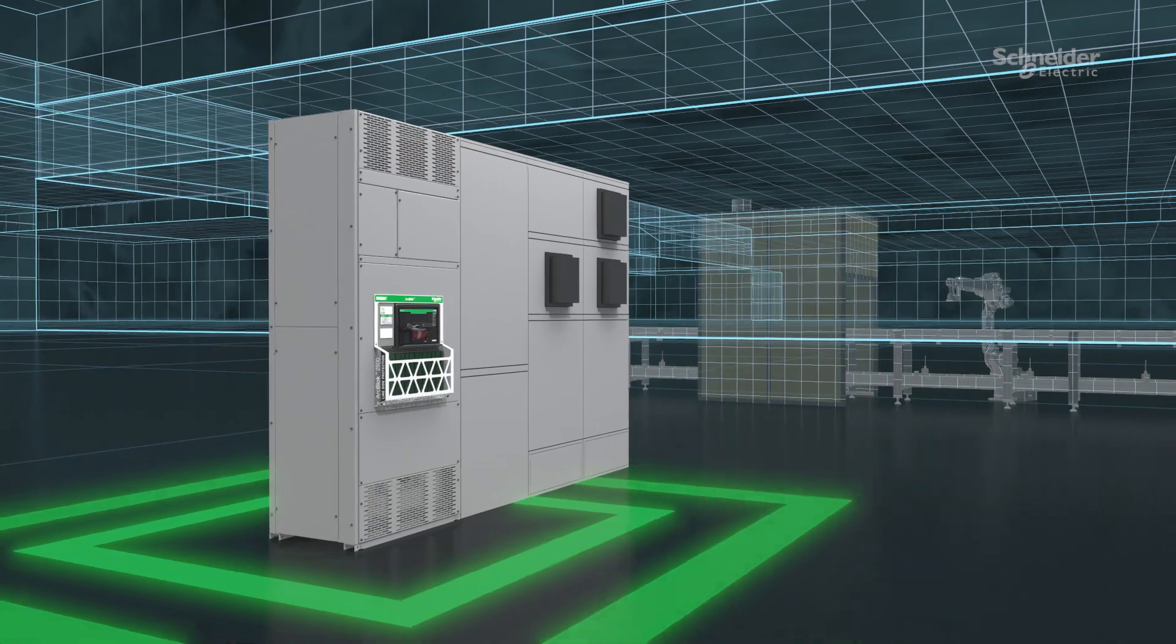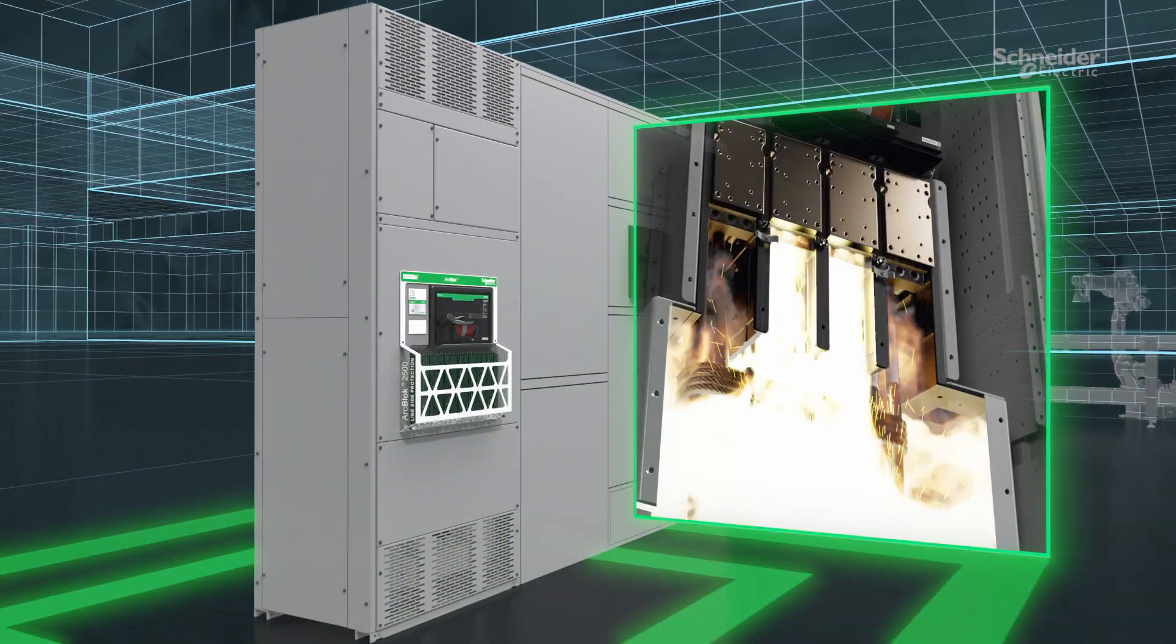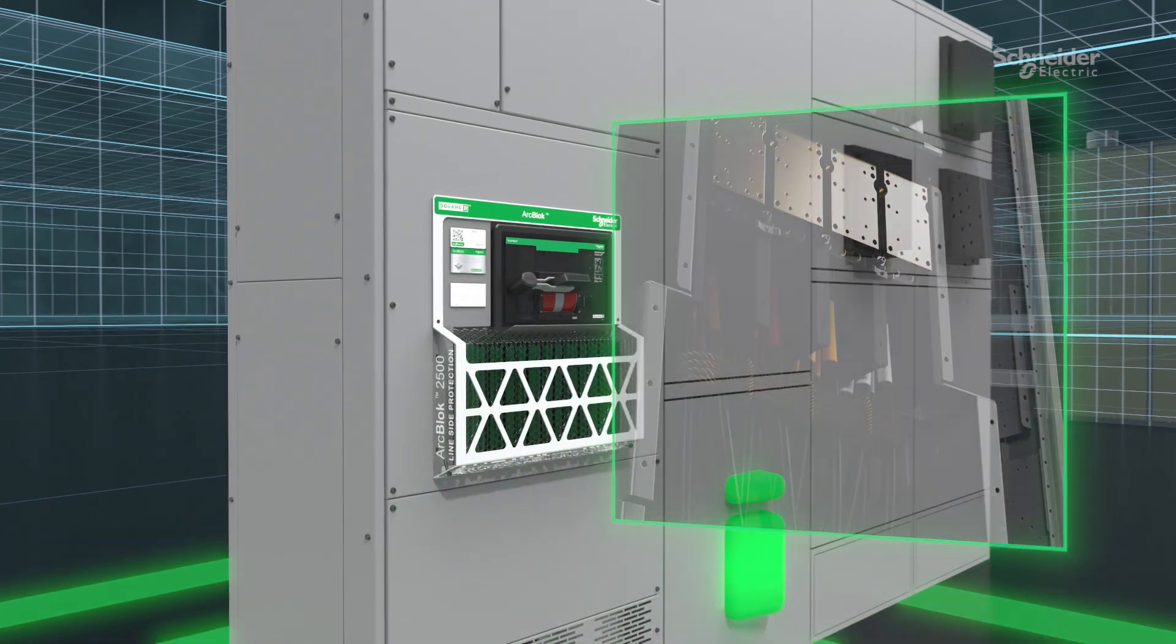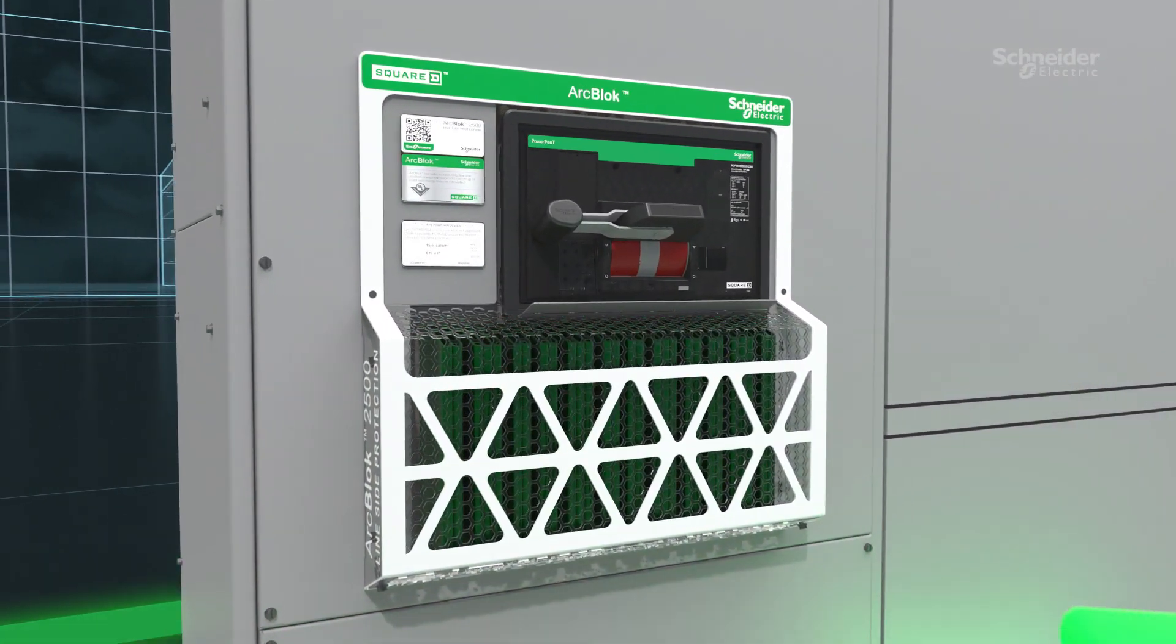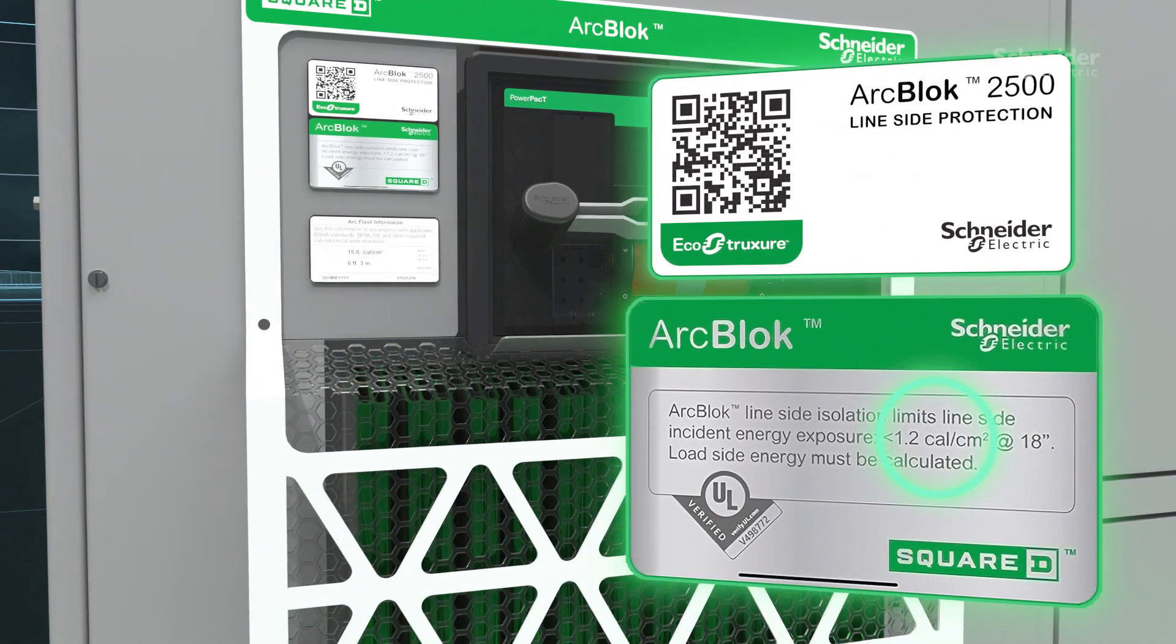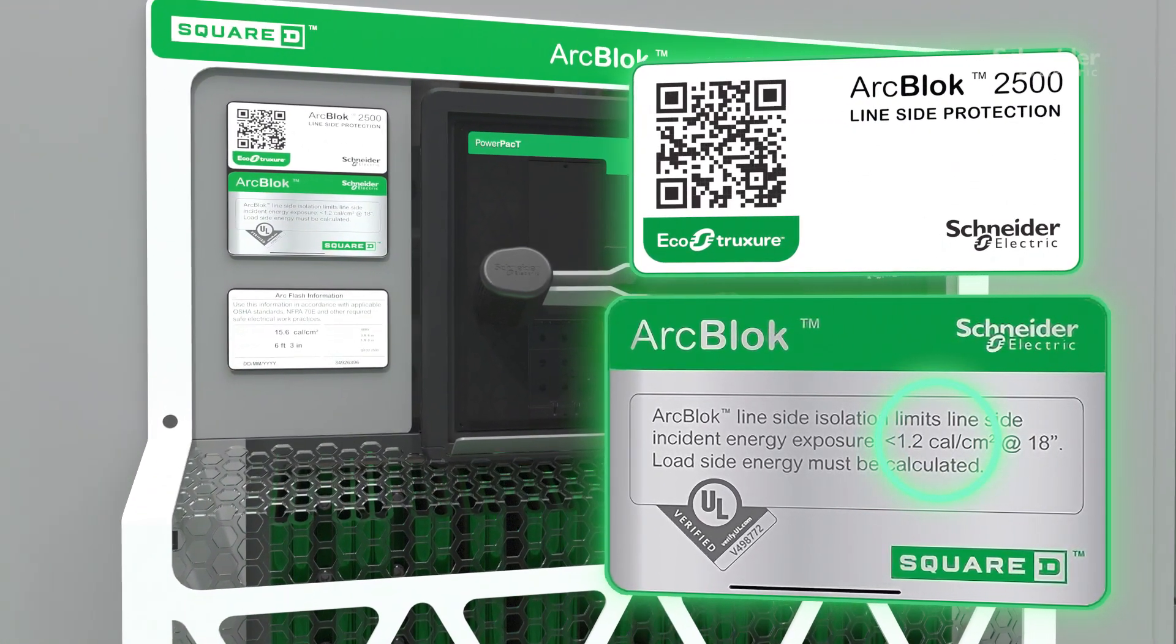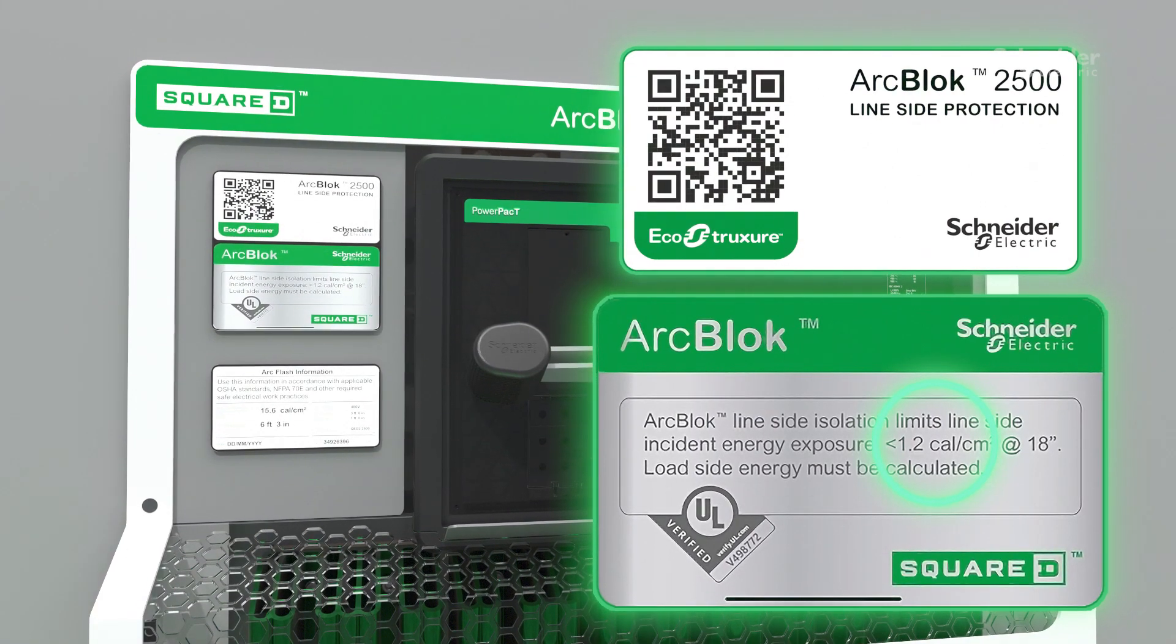These are real measurements recently assessed in an arc flash study at an actual customer facility. Because there is true isolation in the cabinet, labels on the outside of the equipment can reflect the reduction and include the protective device in the equation per IEEE 1584.